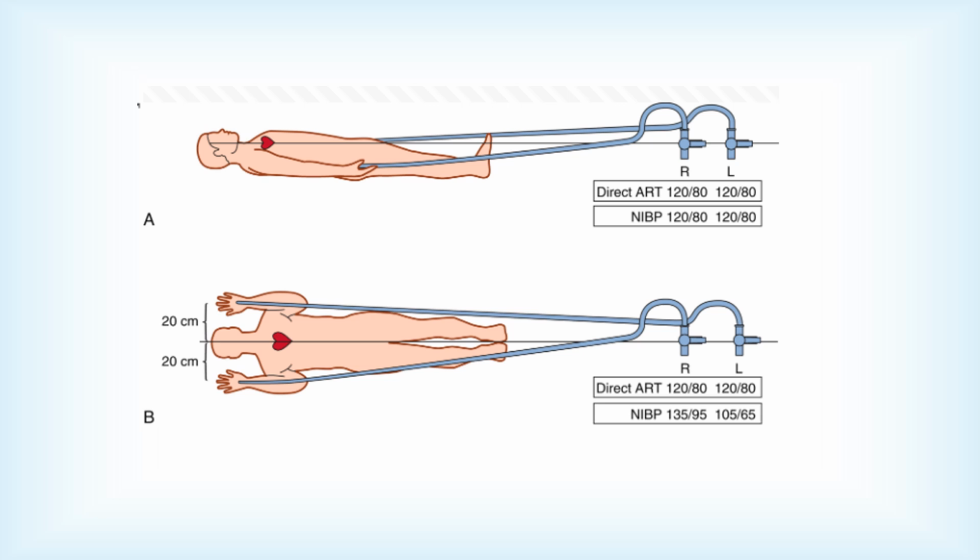If one needs to focus on mean arterial pressure perfusing the brain, which would be lower in a sitting position, for example, one could zero at the heart and move the transducer to the level of the head, or make calculations based off of the height difference.